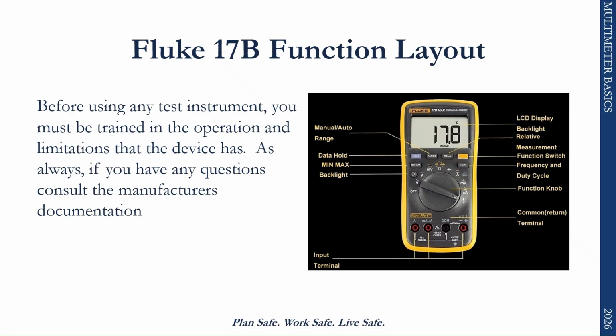Before using any test instrument, it's important to understand how that device works and what its limitations are. The Fluke 17B digital multimeter is a versatile meter used for a variety of electrical measurements, but like any tool, it's only effective if it's used correctly. You should always be familiar with the layout of the meter you're using, where your dial is, where the test lead plugs in, and what each setting is designed to measure. If you're unsure about a function or setting, the safest approach is to stop and consult the manufacturer's documentation or ask someone who is familiar with the equipment. Using a meter incorrectly can result in inaccurate readings, and when we're verifying whether equipment is energized or not, accuracy is critical.